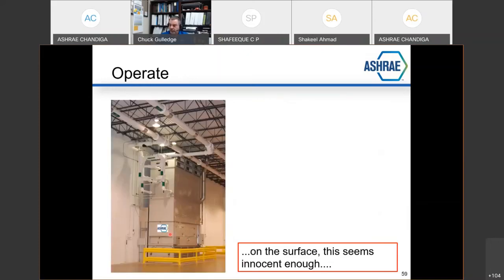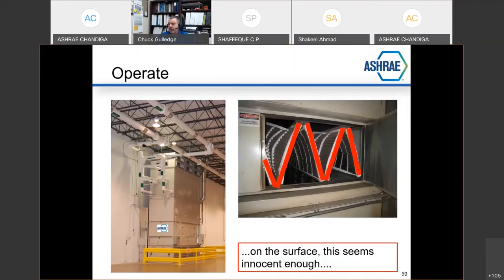On the surface, this seems innocent enough. Look at this beautiful air rotation unit, chill water piping, A-frame coil, industrial quality deep throw drum punka louvers. There are three high volume propeller fans in here. This is full of filters. There's an intake right here, and there's an economizer that comes in low. This is a pretty cool setup. And then you open one of these doors right here, and you see filters that look like this. We got called in to look at one of our design installations, and there was a problem with this air rotation unit. We opened it up, found the filters had collapsed.